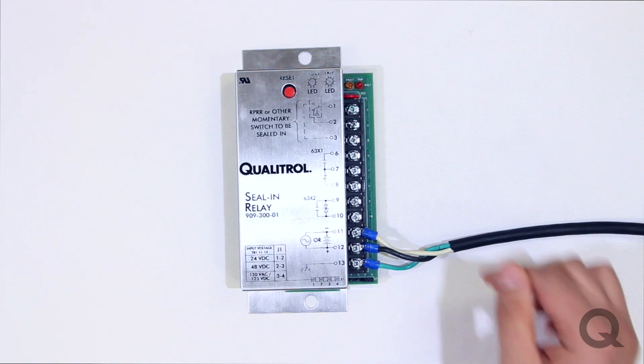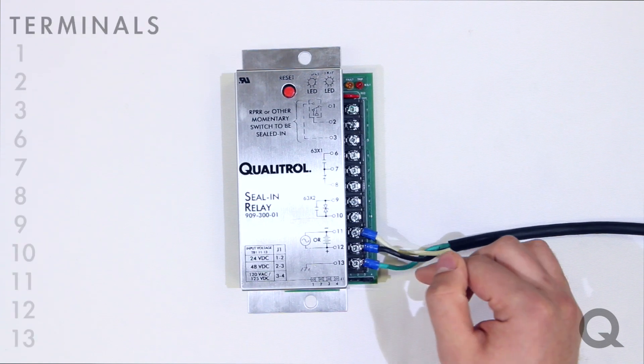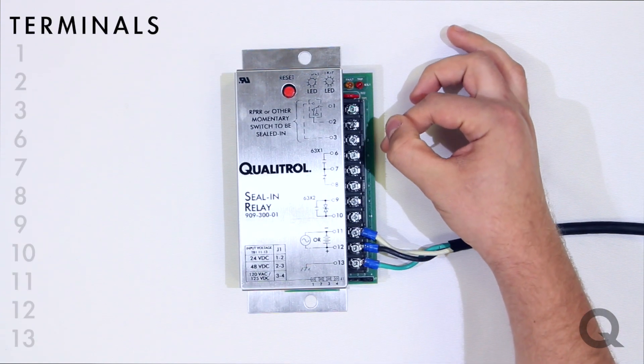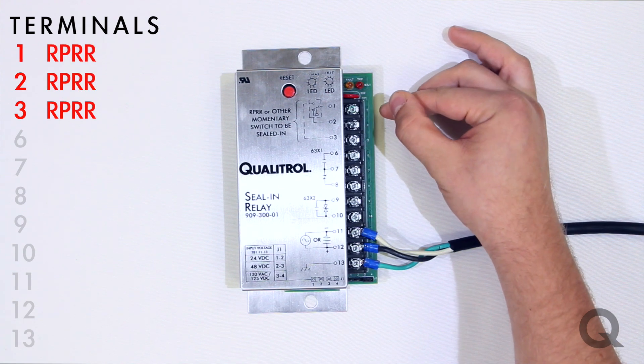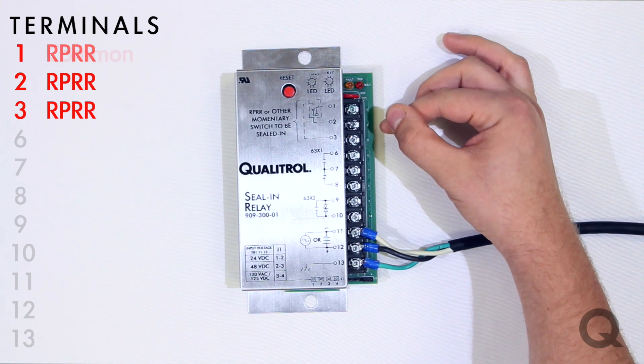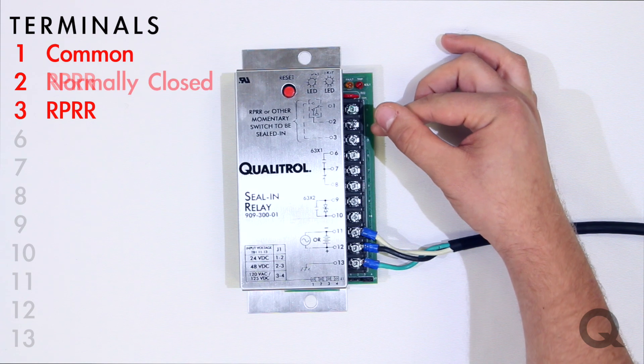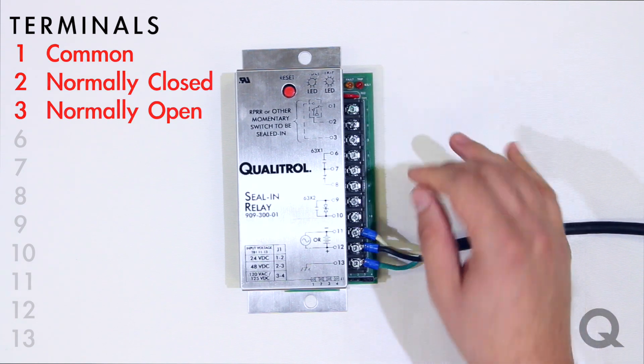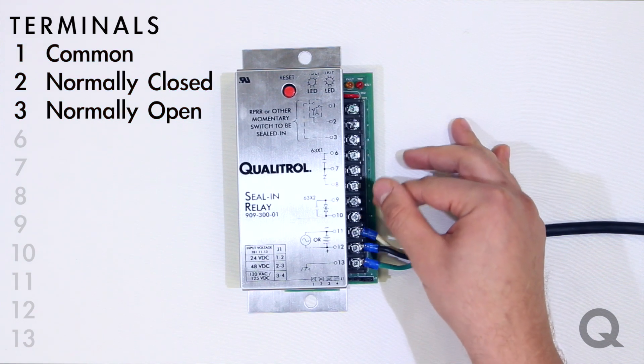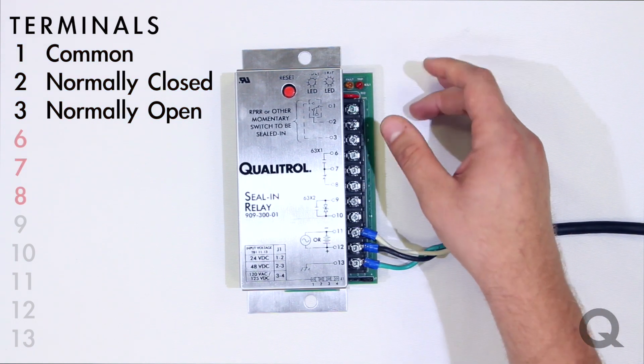All of our seal-in relays have 11 terminals. Terminals 1 through 3 are where you would hook up our rapid pressure rise relay. Terminal 1 is the common, terminal 2 is the normally closed, and terminal 3 is the normally open contact. All seal-in relays have a form C and a form A contact.